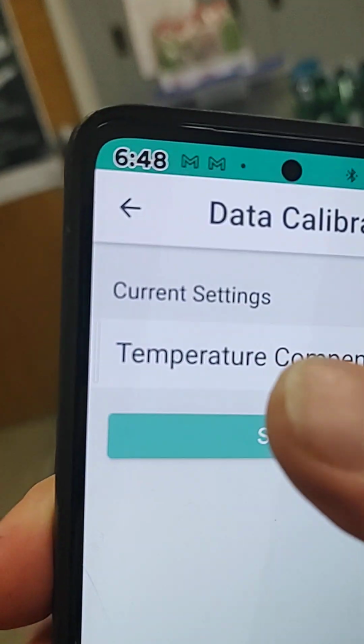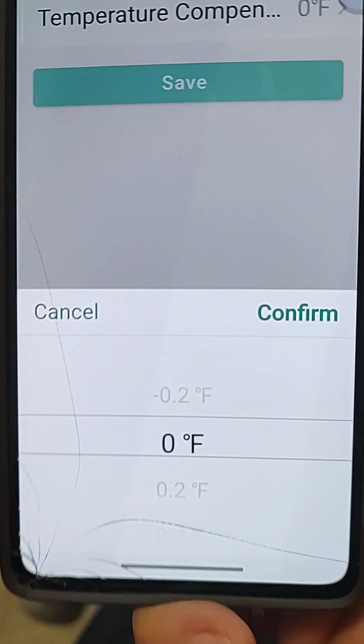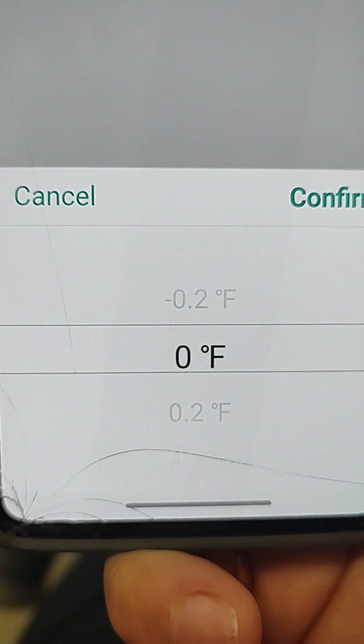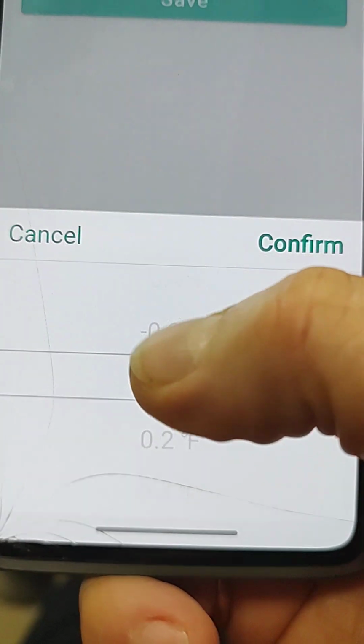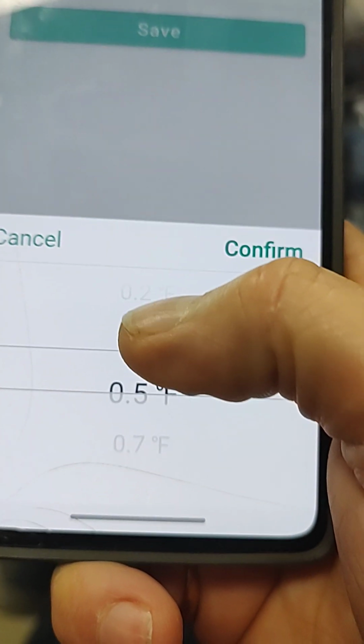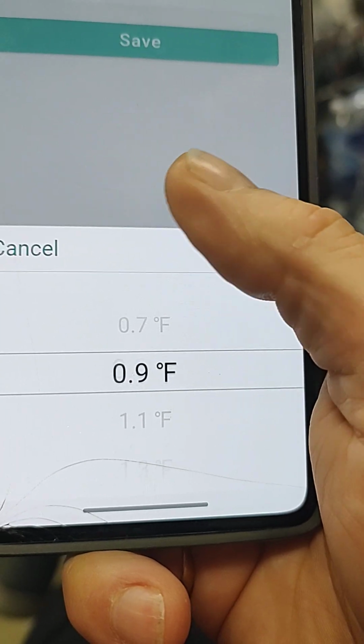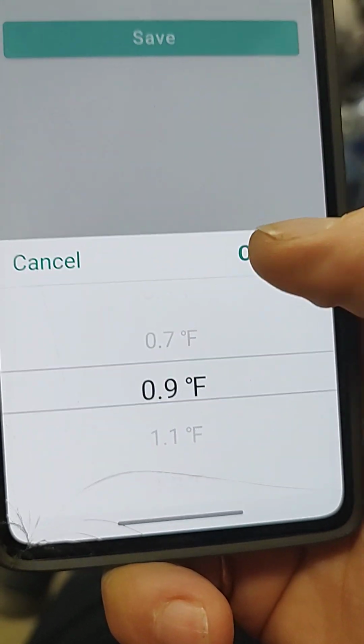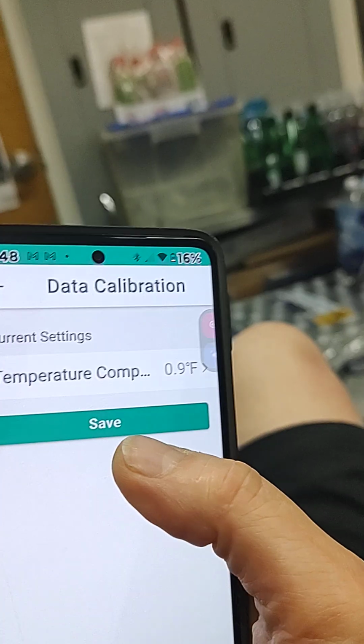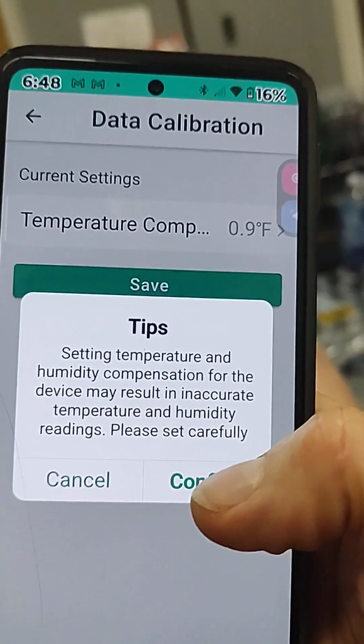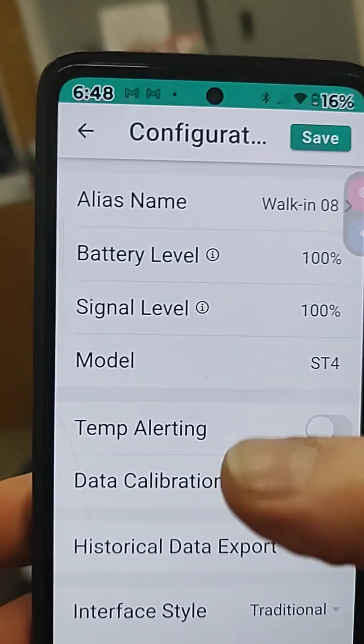So we go into settings, data calibration, and because it's registering 0.9 degrees lower than the ice point, we add 0.9 degrees to the digital output to make the correction. And then we save it, because if you don't save it, it won't do anything.